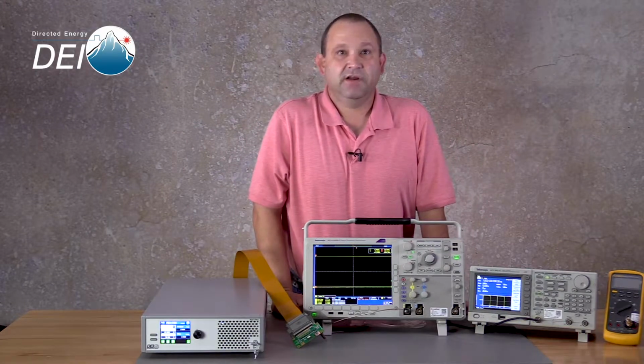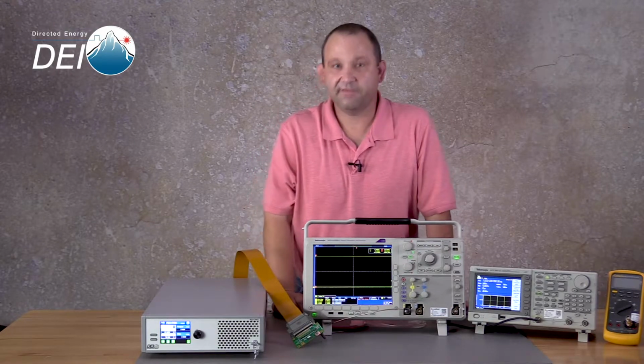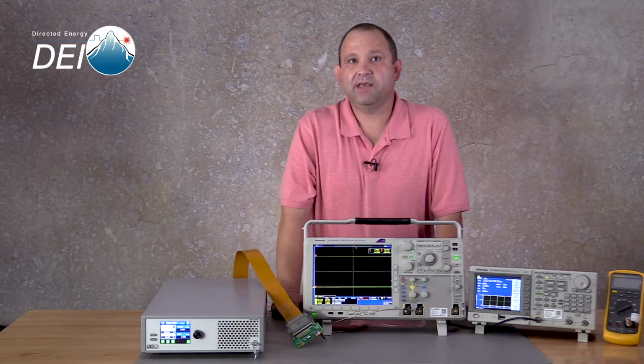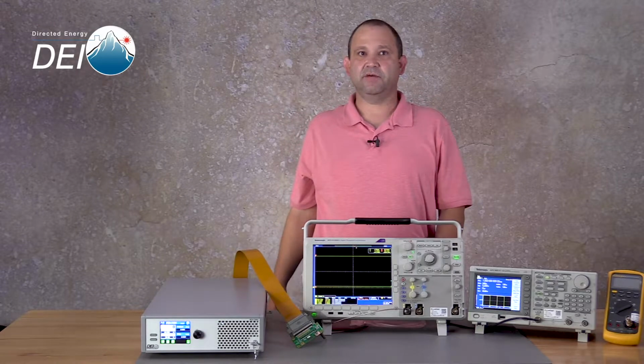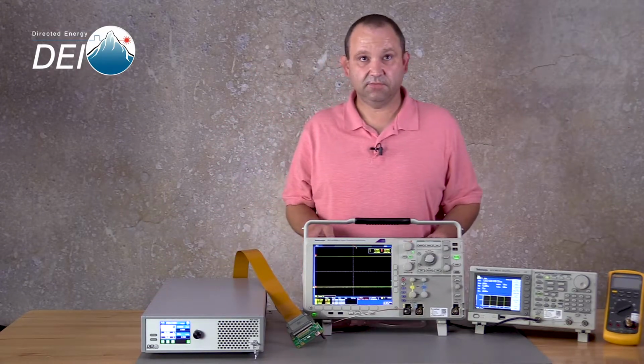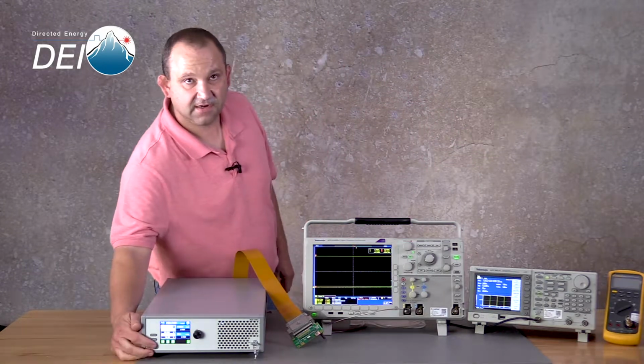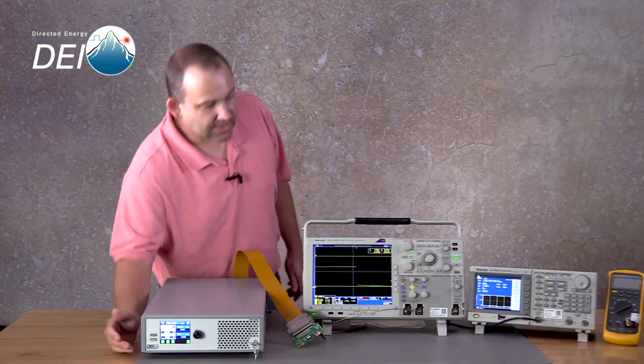All right, we are now going to go ahead and do the live operations. I've already done the first setting and have it set up. I have all my interlocks set to where it will allow this unit to put out a pulse.